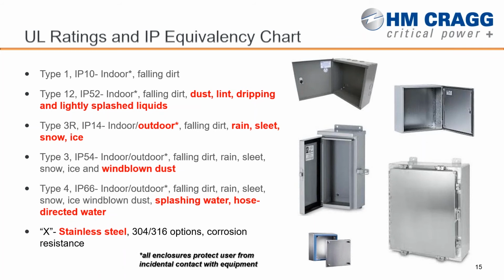So now we've got airtight. You can hose it down, you can wash it down. If you're putting it into an emergency application, like emergency telecom communications for the fire department or first responders, those enclosures have to carry this type 4 rating, because as the fire department comes through the building, if it's on fire, they're going to be spraying water everywhere. And you've got to make sure that none of that gets into the equipment and shorts out the radios that those guys are using to keep in contact with one another.